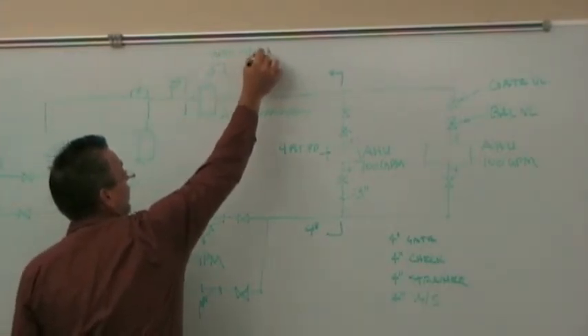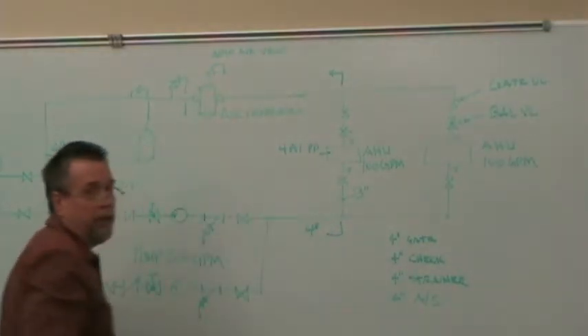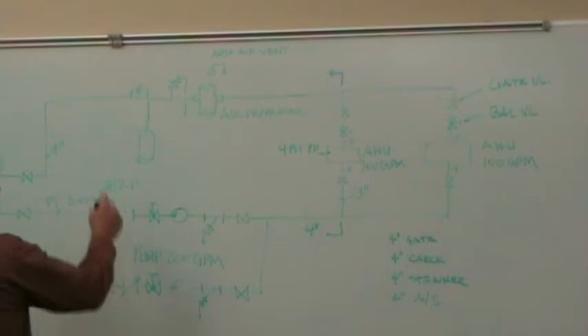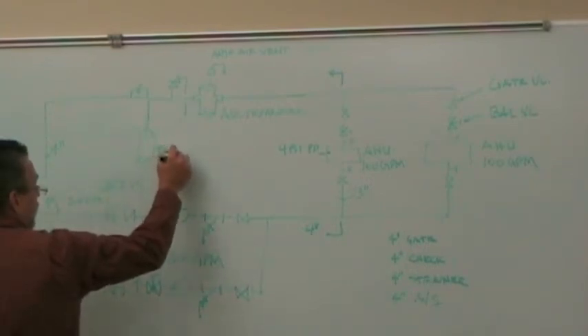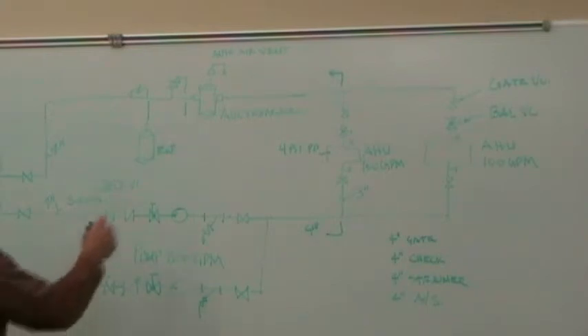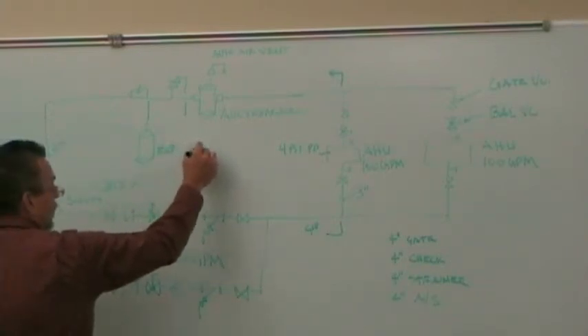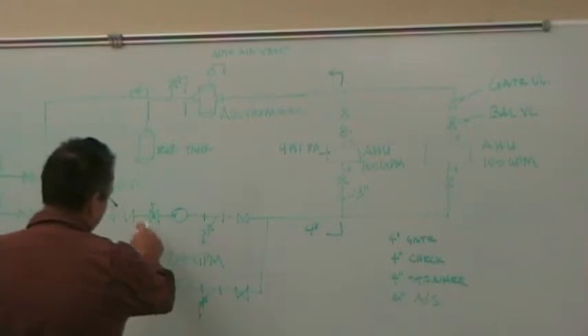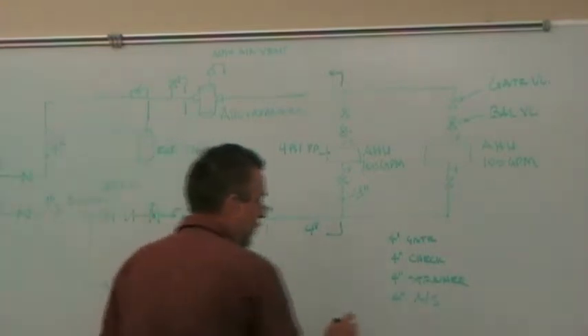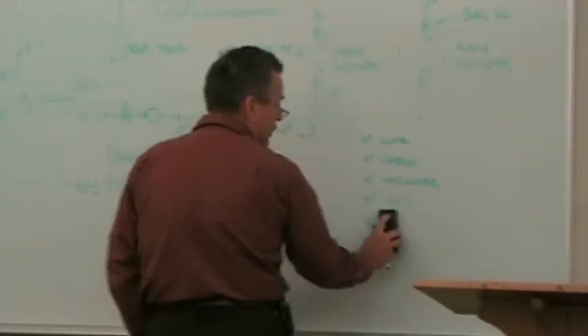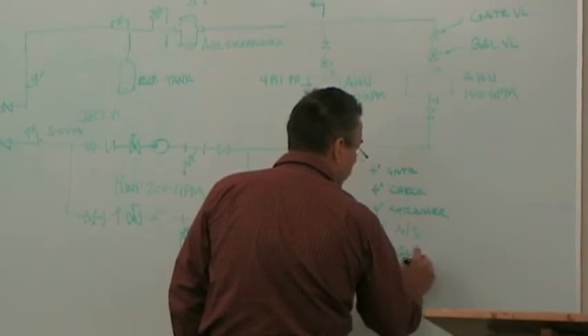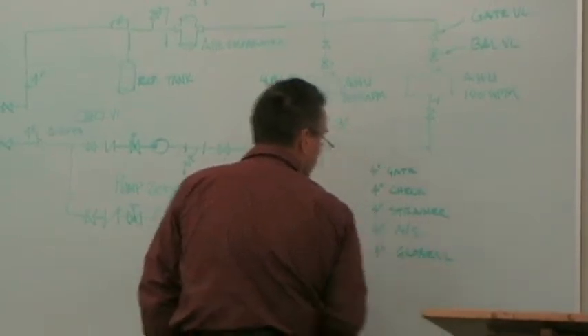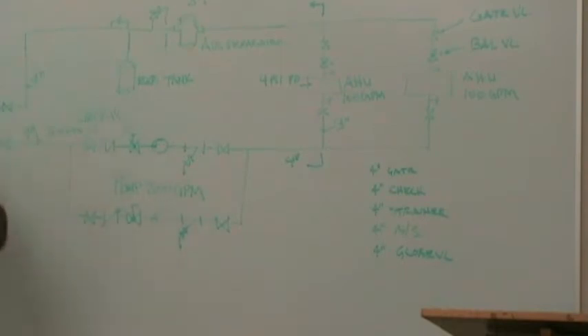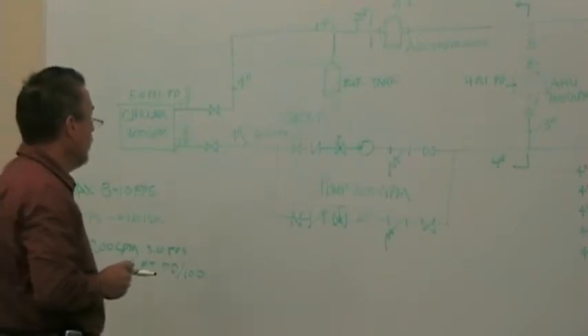And that spits and bleeds to a drain. I've got my expansion tank. Of course, it's not in the line, so it doesn't affect the pressure drop. And I've got balancing valves. Could be any kind of balancing valve. We'll just say globe valves. Go back here, 4-inch globe valve. Okay. Pete's plugs, thermometers, they're not in the line. The T is so small, it doesn't affect anything.